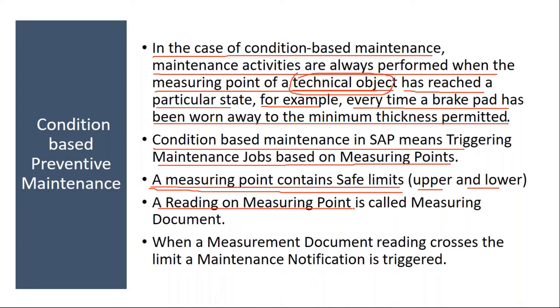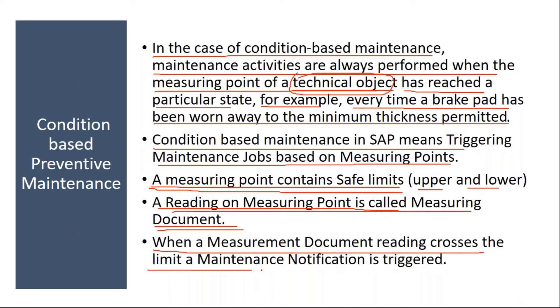A reading on a measuring point is called a measurement document. When they take the measurement — suppose they want to measure temperature — that reading is entered in the system using a measurement document. This we also covered in our master data sessions. When a measurement document reading crosses the limit, a maintenance notification is triggered.